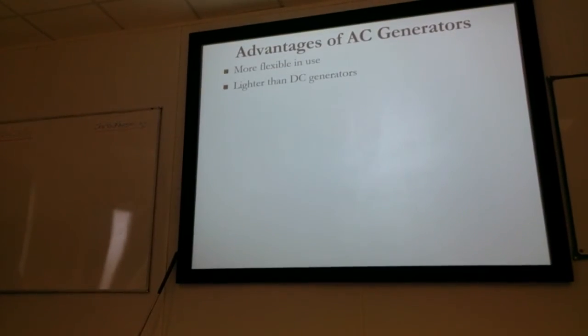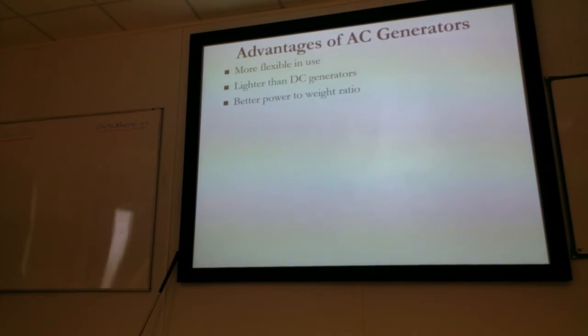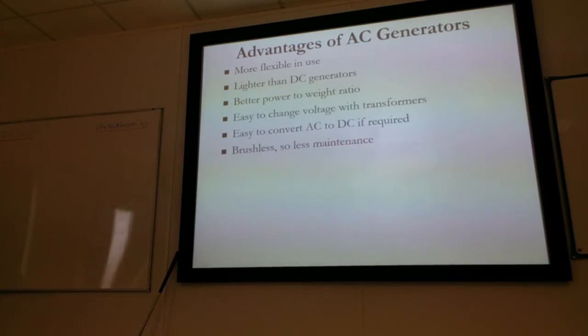AC generators then, okay. They are more flexible in use than DC generators. You can do things more easily with them. They're also lighter than DC generators. They have a better power to weight ratio. It's very easy to change the voltage using transformers, so they're versatile. It's also fairly straightforward to convert AC to DC if that's required. Brushless, they tend to use constant contact slip rings rather than carbon brushes and commutators, so less maintenance. They're working for you at lower RPM than DC generators would be, so that's a good thing.